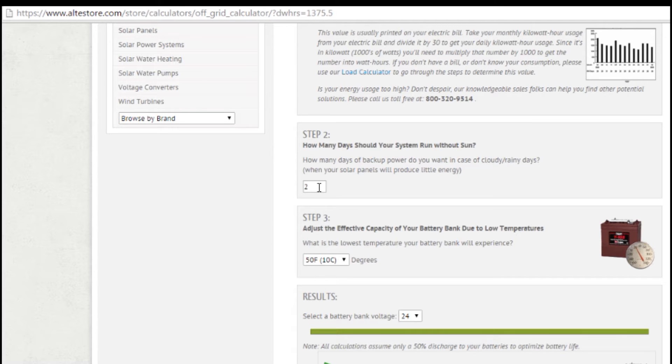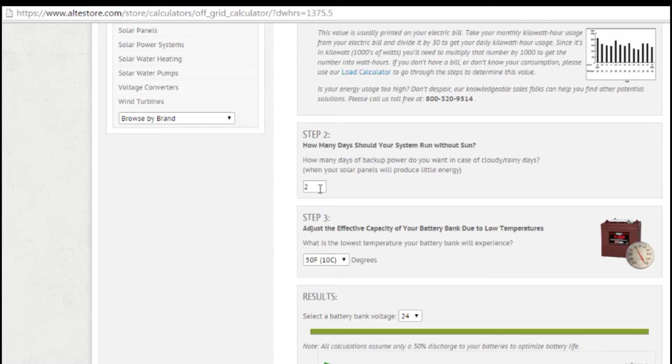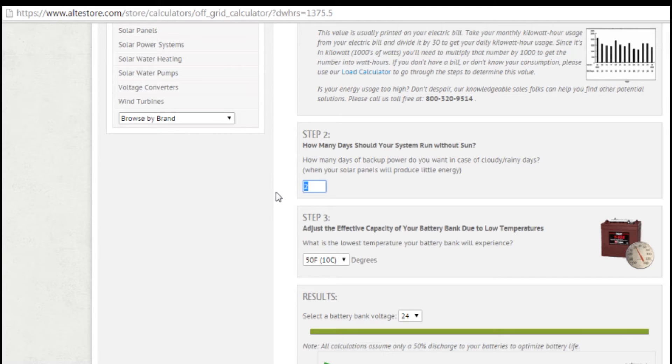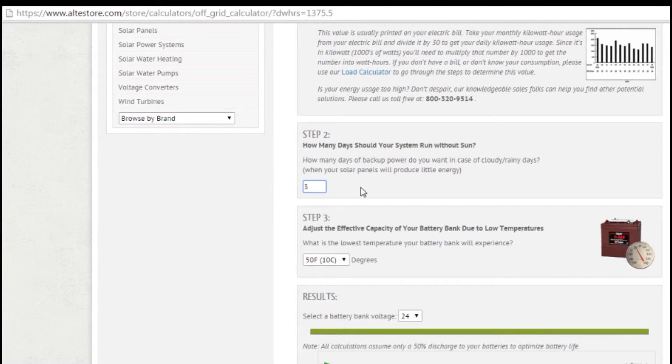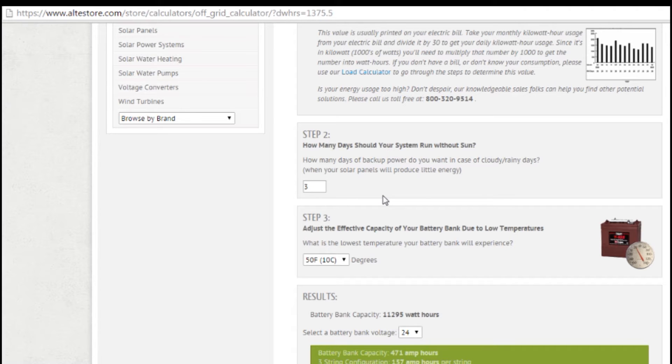If you're doing an off-grid home that you want to minimize the amount of time that your generator runs, you might choose five days depending on how often it is that you would actually have a long stretch of bad weather. A common number that's kind of a compromise between them is to do three days, and that will give you the ability to run for three days without any power from the sun or from a generator. And if you go a fourth day, you would just have to fire up your generator.